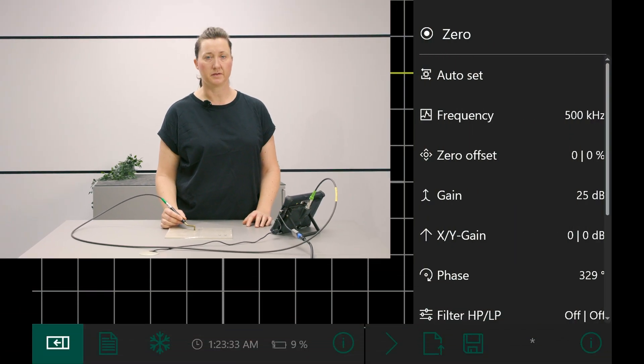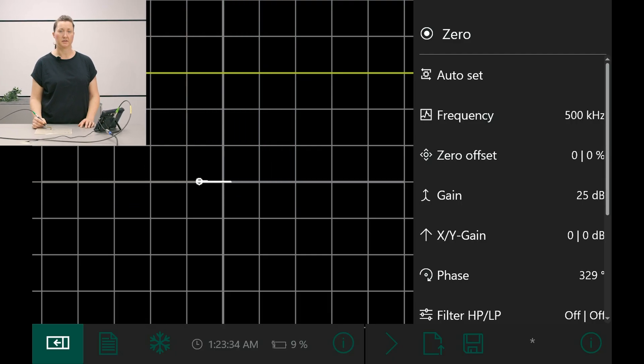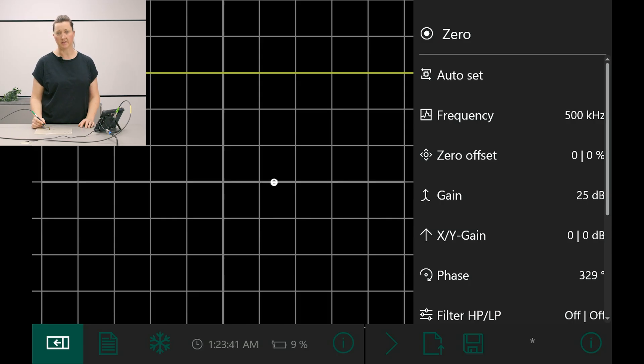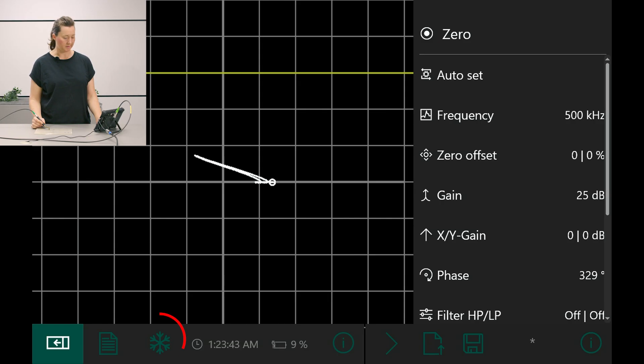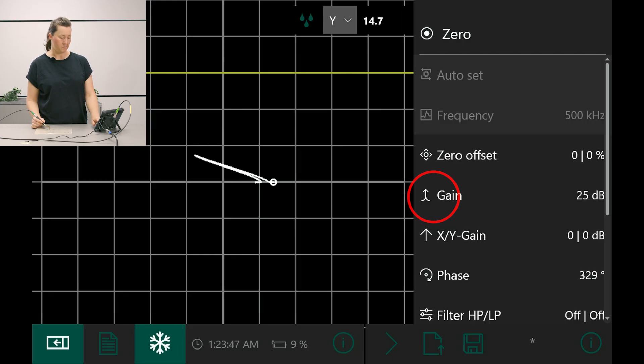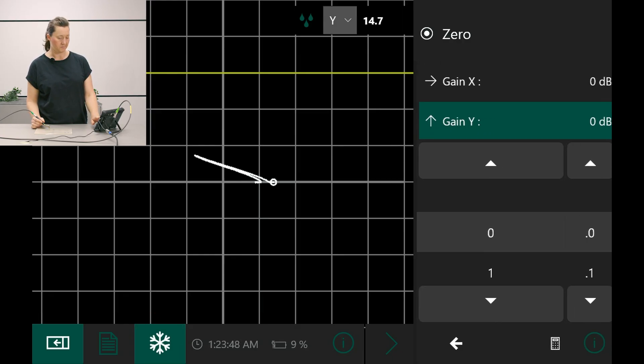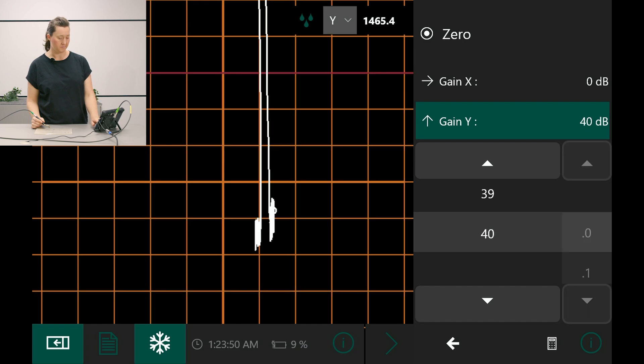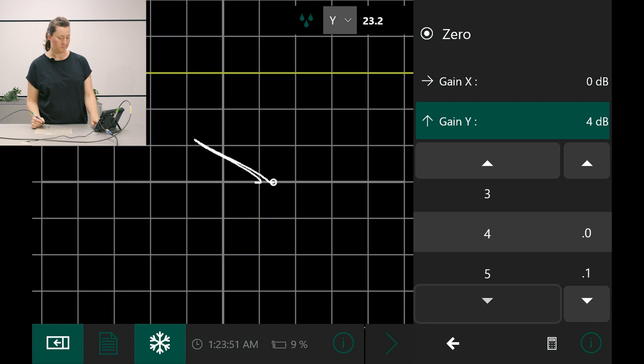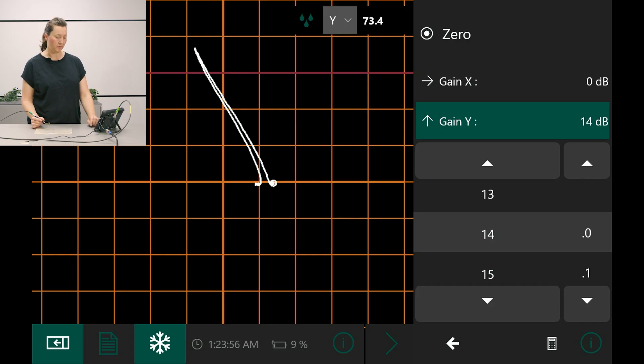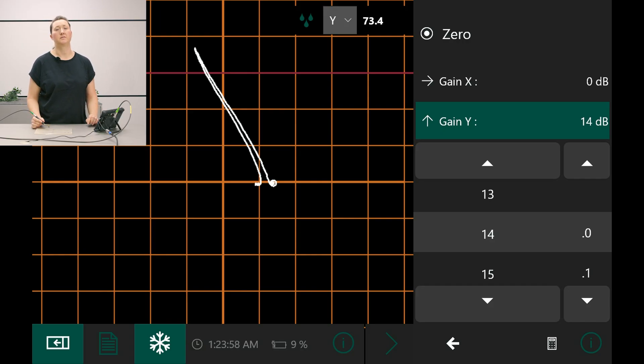We would like to detect a 0.5 mm deep crack. In the moment the crack signal stays below the 60% threshold. With the gain function I can change the height of the signal. I freeze the crack signal again using the snowflake icon and increase the gain. With the gain of 14 dB the threshold is exceeded.